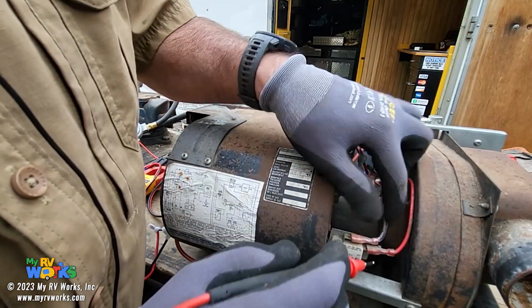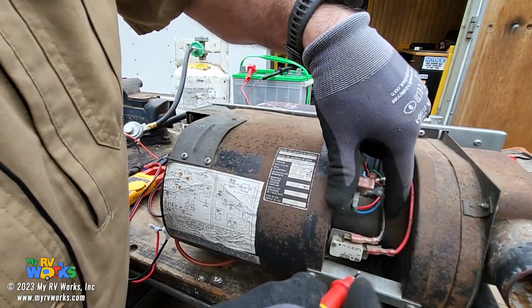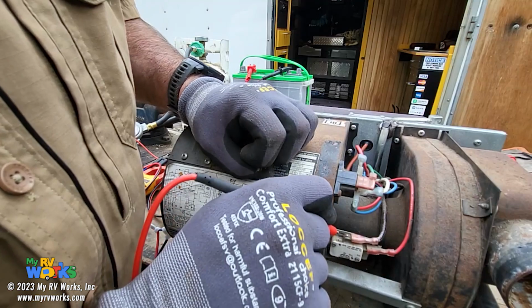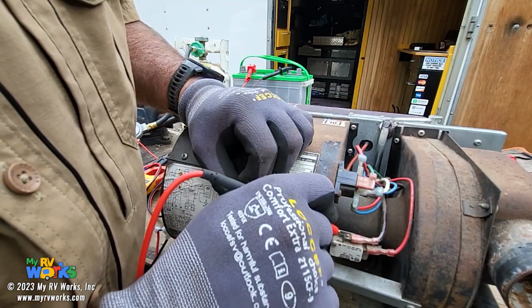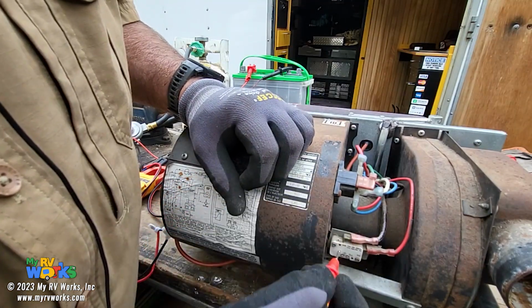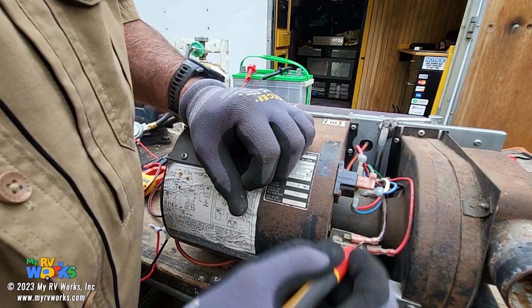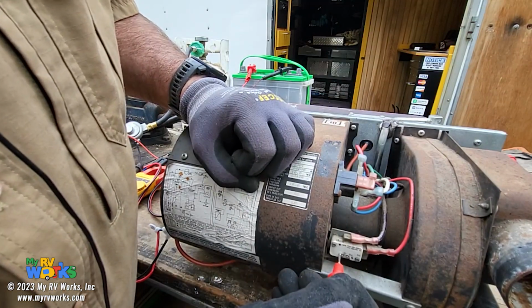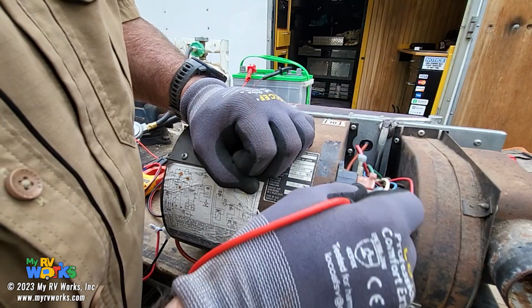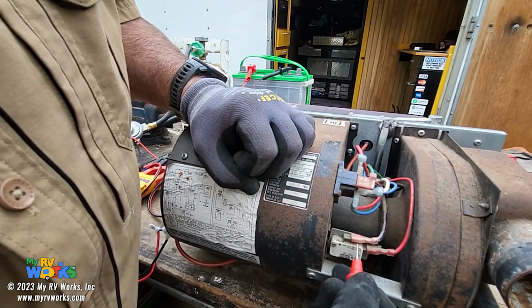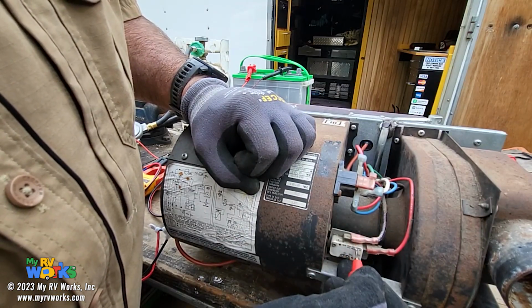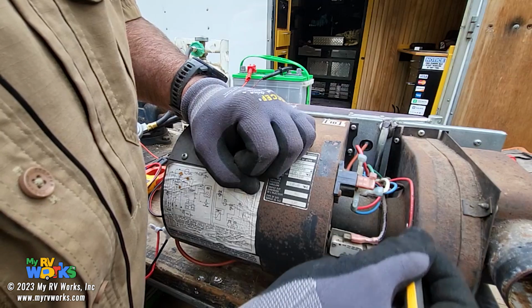I come back on this black wire with the high temperature braid, sitting right here on the pin of my sail switch. The sail switch is open, so it just sits, waiting for the motor to start. When the motor starts, the sail switch closes, allowing 12 volts to pass through onto this red wire.